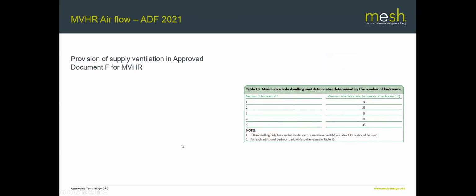So how much air do we actually have to supply? Well, you have to meet two criteria in the approved document. First of all, you have to meet the criteria shown in table 1.3, which is this table here. That just gives you a supply rate in litres per second based on the number of bedrooms. So if you have a 4-bedroom house, for example, your air supply rate must be at a very minimum 37 litres per second. Well, 37 litres per second isn't an awful lot for a 4-bedroom house, especially one which has reasonable sized rooms.